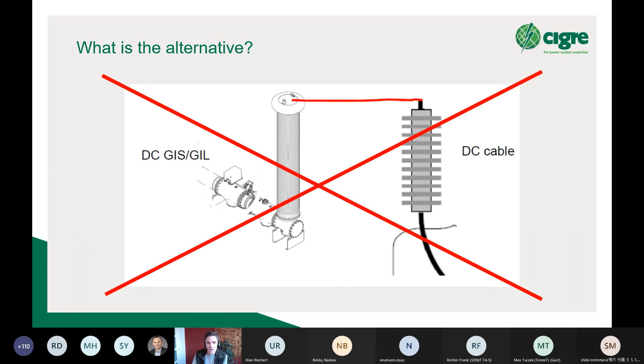Now, the good news is that several designs for HVDC GIS cable connection assemblies exist, and they can follow similar sort of high-level arrangements as you see in AC. So we have, for example, dry type terminations or so-called fluid-filled terminations, which for DC are mostly not filled with fluid but with a gas, SF6. And then there are also some designs where the type has not been disclosed, so who knows what's inside.